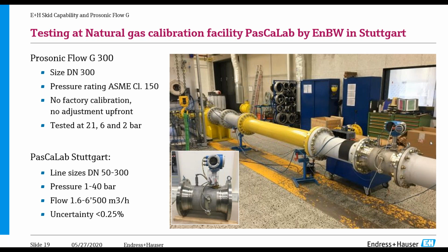It was just by design, we measured all the tolerances. We take great care to make sure that each meter is very precisely made. This is especially true on the transducers. We measure each and every single one of them to make sure it maintains a certain tolerance. If there should be a failure on a transducer, you can put a replacement one in and it will be the exact same dimensions. You do not need to recalibrate the meter. But continuing on about testing of the meter, we tested it at 3 different pressures, and the uncertainty of the rig at PasCaLab is 0.25%.